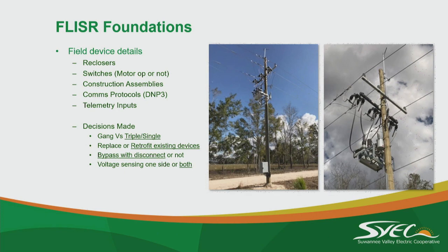What we did - anywhere we needed a switch or a two-way feed, we just put a recloser and programmed it as a switch. That way, if we're feeding a different direction, we could turn that into a recloser. Everything's there, you just do another settings profile in the relay.